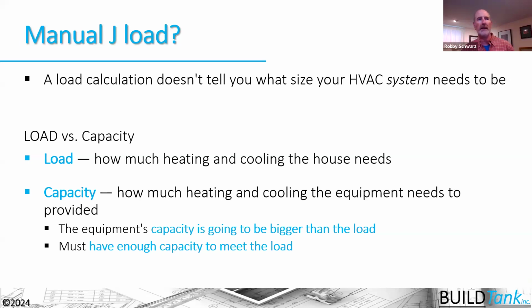So the load ultimately tells me how much heating and cooling energy I need for that particular house to keep that house comfortable during the worst case components of our yearly environment. But it also helps us figure out how big of an HVAC system we need to install. So that system has to have the capacity to meet the heating and cooling loads of that house over the course of that heating season. So often the equipment's capacity is going to be a little bit bigger than the load, and we must have enough ultimate capacity to meet the load.